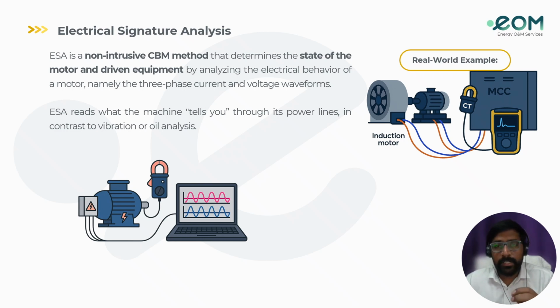If we see a real-world scenario in a cement plant where we can't stop a 4 kilowatt ID fan motor to install a sensor, then we use a clamp-on CT at the MCC to feed line current to a portable analyzer. There the spectrum shows the rotor fault sidebands. Then the maintenance is planned outage, instead of risking a trip.